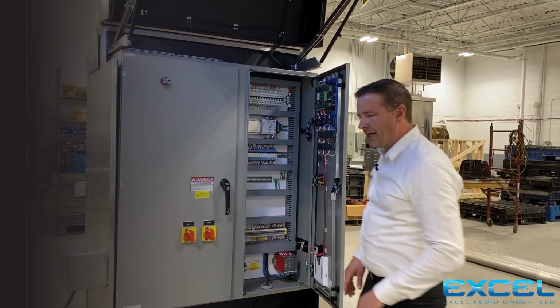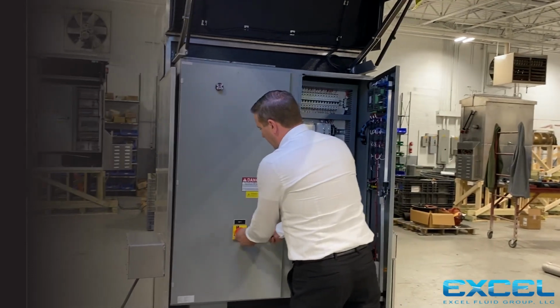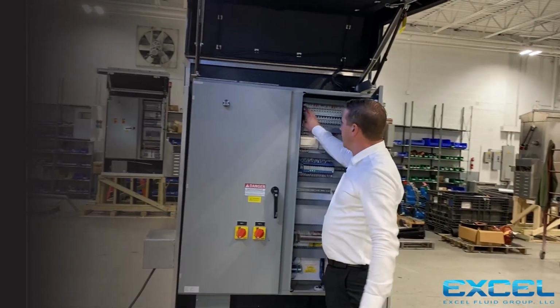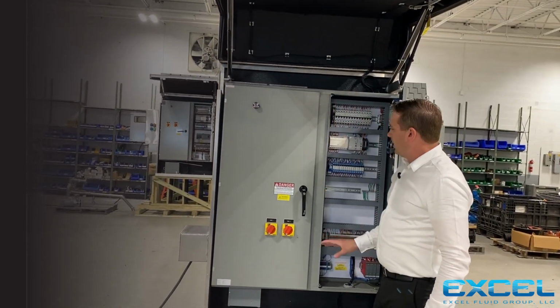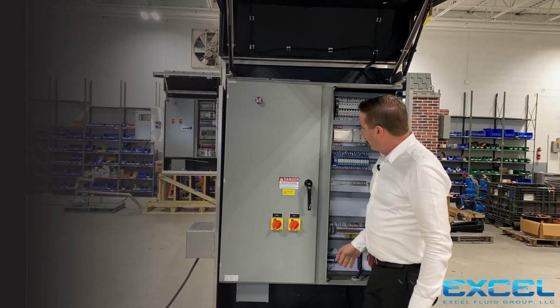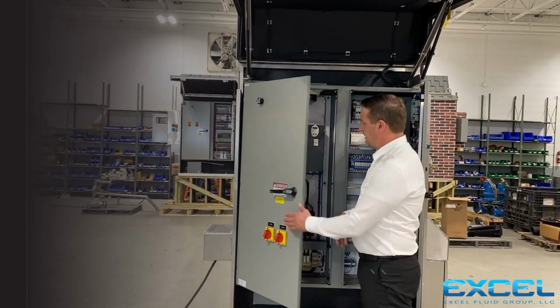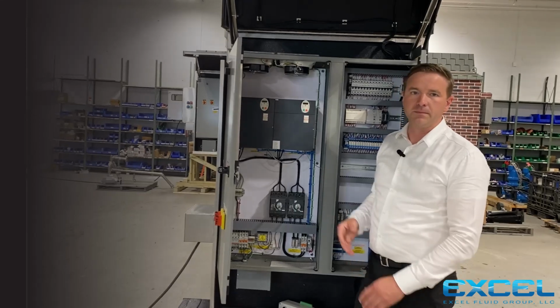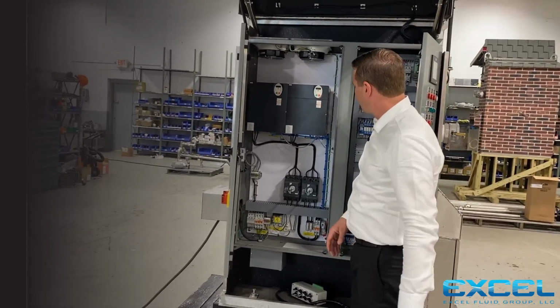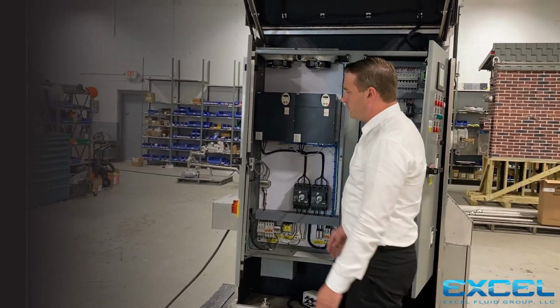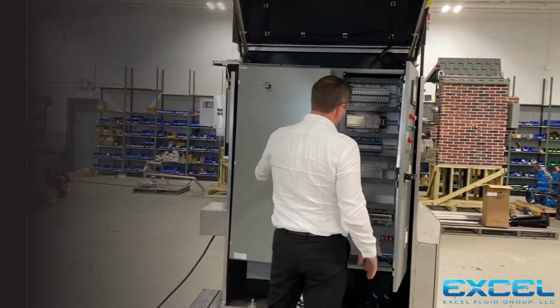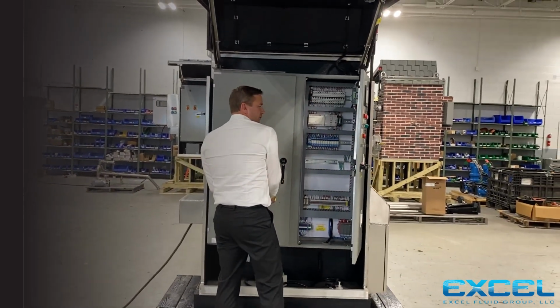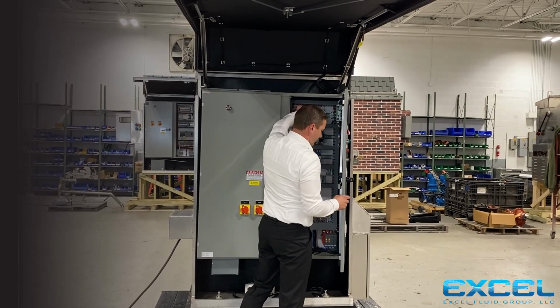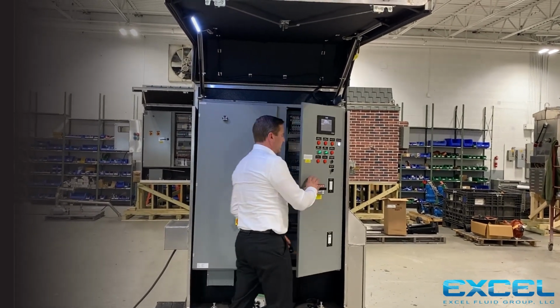When we want to access the high voltage side, we shut down our pumps, we de-energize the station. That releases the electromechanical interlock and gets us access to VFDs in this case. Could be soft starts, NEMA starters. Ventilated control, avoiding arc flash hazard, keeping the operator in the low voltage side when he needs to be operating the station or maintenance.